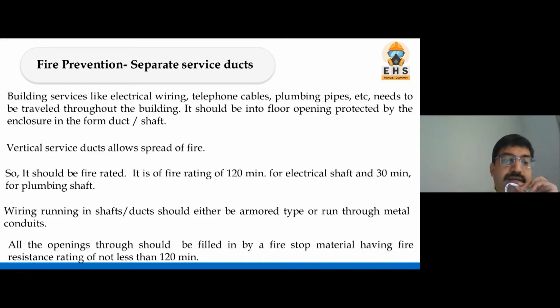Now wiring running in the shaft should either be armored type or run through metal conduits. So this is also important. Means it should not be normal wiring, because if something has happened, then it is very difficult to control the fire again. So from a fire prevention point of view, whatever these wirings are, it is expected that they are either armor type or, if not, then through metal conduits. All the openings should be filled with fire stop material having fire resistance of 120 minutes.